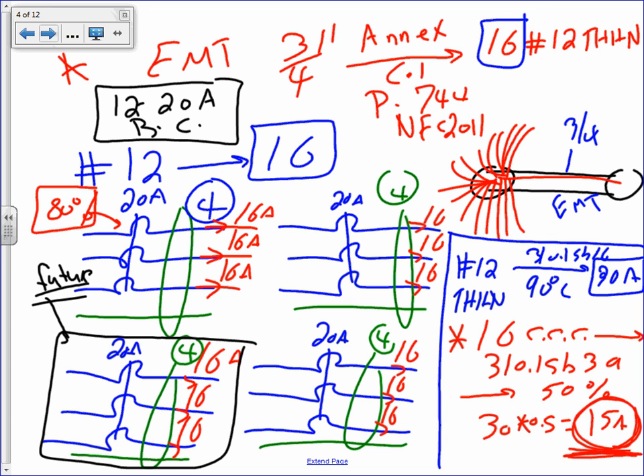Now, how many carrying conductors do I have here? Assuming these are feeding harmonics, the neutral counts. How many of them do I have? I have 4, 4, 4, 4. 4 times 4 is what? 16. Okay? All right, so take number 12 conductor, give you 30 amps. 16 carrying conductors. Everybody knows why 16? Because all these circuits that you're looking at, I group them in one conduit.